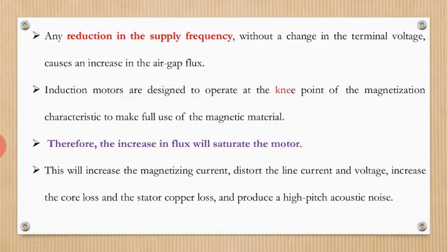Usually induction motors are designed to operate at the knee point of magnetization. To make full use of the magnetic material, they use the knee point of magnetization. We can't go beyond that value of air gap flux.